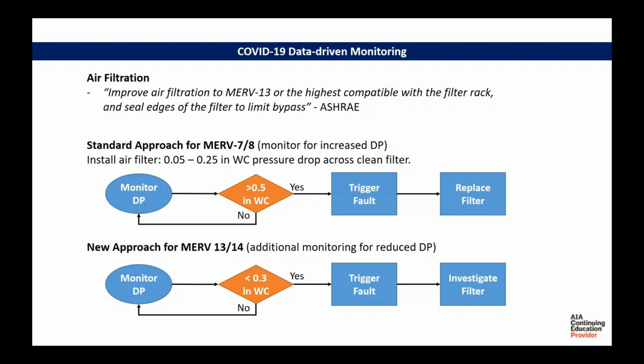So now the guidance here is that we want to have higher efficiency filters, so MERV 13 or higher. And let's assume we can install those filters. And that is an assumption because filter racks are different width and they can't all house the same filter. So let's just assume it is going to fit. Now this MERV 13 or 14 filter goes in with a clean pressure drop of 0.3 or maybe a little more. But now that we have that information, we can continue monitoring for dirty. Maybe it's not 0.5, it's 0.6. But what we can also do is monitor that differential pressure or that pressure drop to make sure it doesn't decrease. So now we know if it goes below the pressure drop when it was installed, that there's air bypass or that the filter has been dislodged. So we're using the data we already have and we're looking at it slightly differently. And instead of looking for energy gain, there's just that safety-minded analytic to just make sure that the filter is still there and all your air is still passing through the filter as it's supposed to.